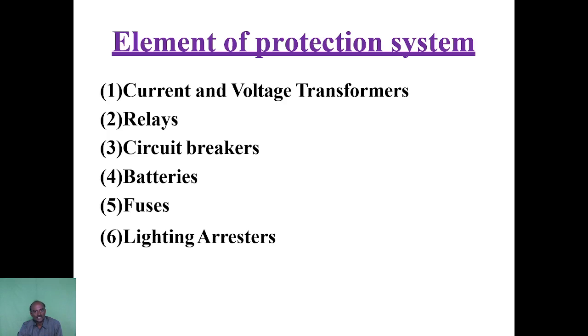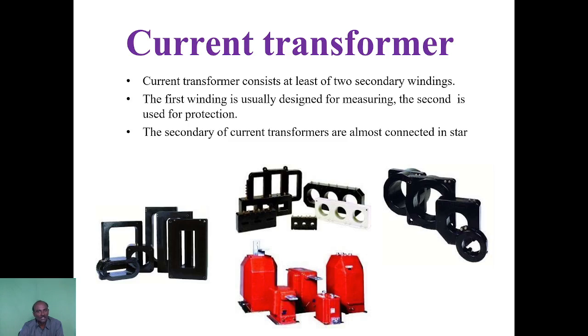So what are the various elements in the protection system? Current and voltage transformers for measuring current. When sensing the current and voltages, they give current and voltage outputs from the transformers. Relays mainly actuate the circuit breakers. Circuit breakers are used to break or reclose the element which is being affected. Batteries for energizing purposes. Fuses are involved for primary protection, and also lightning arrestors. So these are the main elements of protection.